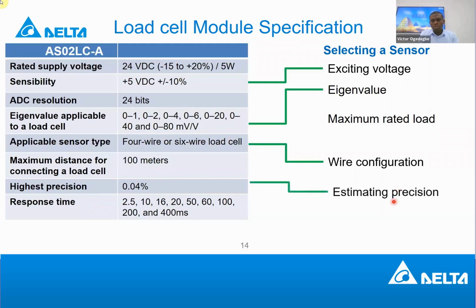And then you also have the precision. For us, the precision is very high. If you multiply this with the Eigenvalue and with the excitation voltage, you have an indication of how precise your measurement will be. For different load cell modules, we have 0.04%, for different modules, not for ours, maybe another brand.